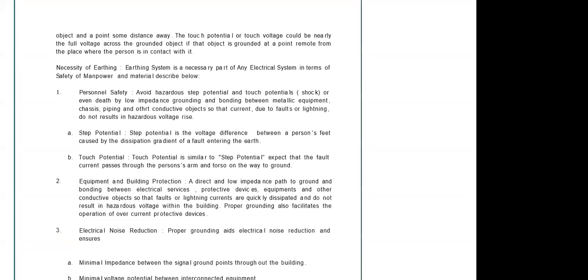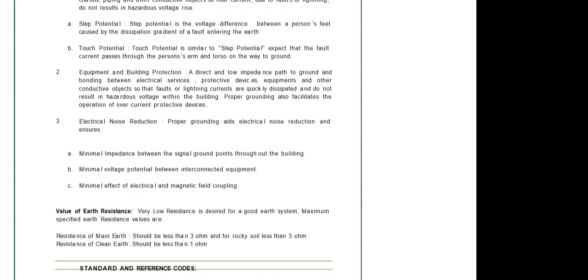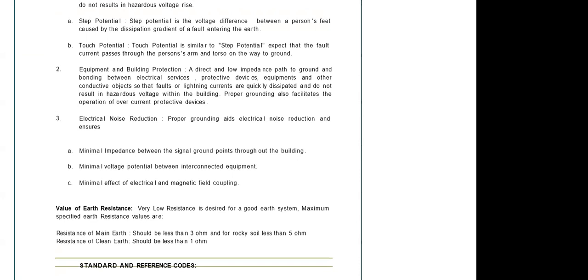Step potential and touch potential, I have already discussed. Next, equipment and building protection: a direct and low impedance path to ground and bonding between electrical services is required to achieve this. Next is electrical noise reduction. Proper grounding aids electrical noise reduction, and again, I will explain this where we deal with VFD drives, which is very important to reduce the ripple or harmonics, what we normally say. The whole idea is to provide an impedance to avoid the shock, this effect of step and touch potential. And the last one is a minimal effect of electrical and magnetic field coupling.